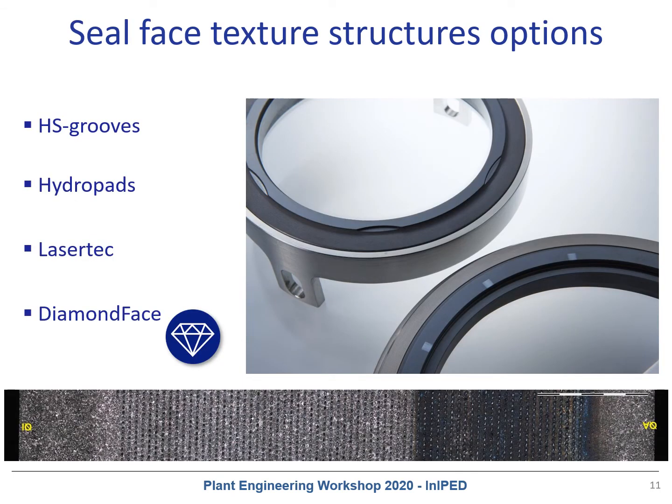There are different options for seal face texture structures, like hydrodynamic grooves or hydropads — also shown in this picture — laser texturing, shown here at the bottom, or even a special material called diamond face. All of these are used to ensure a proper fluid film between the mechanical seal faces.